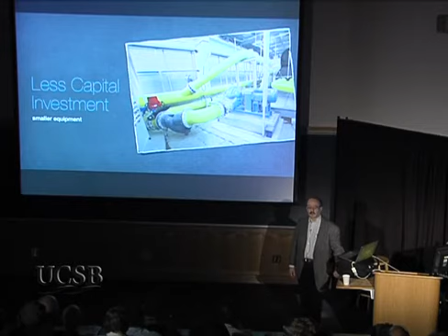But first, we ought to be capturing bigger, cheaper savings that are normally ignored, not in official studies, not in the textbooks. For example, pumps, the biggest use of motors, move liquids through pipes. A standard industrial pumping loop was redesigned to save at least 86% of its pumping energy, not by getting better pumps or motors, but just by replacing long, thin, crooked pipes with fat, short, straight pipes. That also shrinks the pumping equipment and its capital costs. So this is not about new technology.